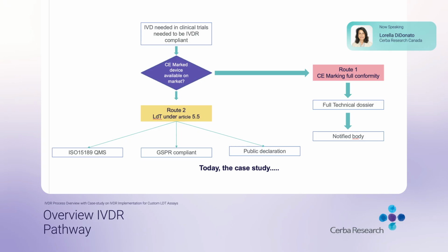This means that the laboratories must take much greater responsibility, and this requires meeting specific conditions under the LDT pathway. These conditions include implementation of ISO 15189 quality compliance with a quality management system, ensuring the general safety and performance requirements, the GSPR compliance, as well as issuing a public declaration documenting adherence to the regulatory requirements.